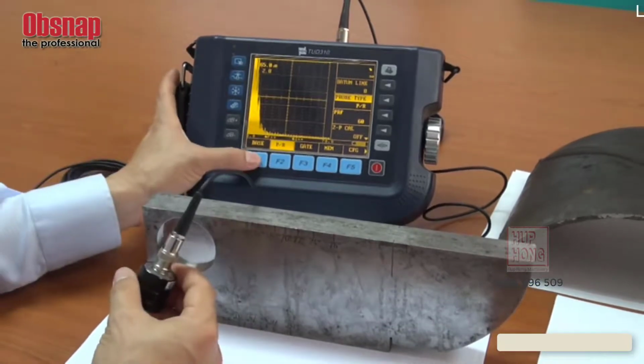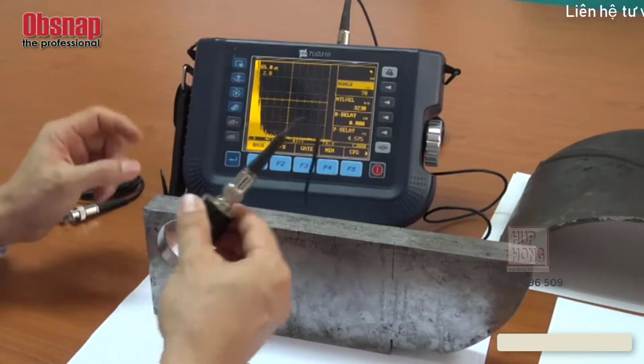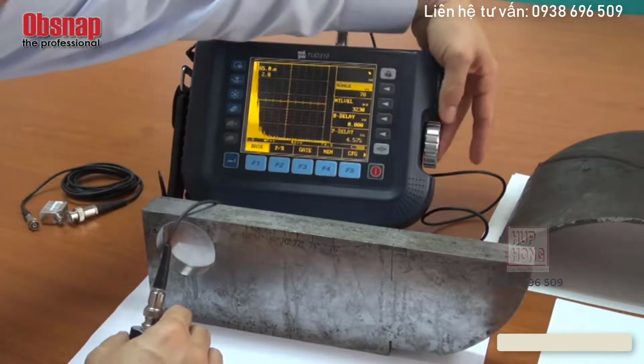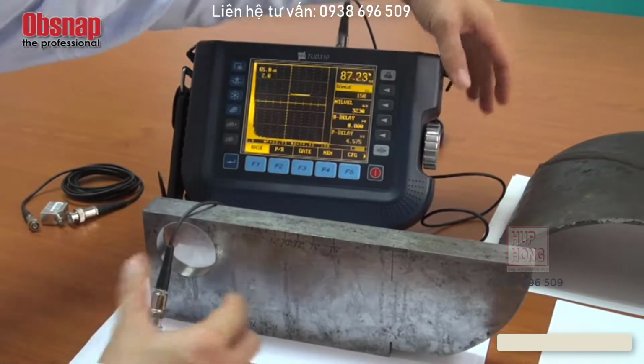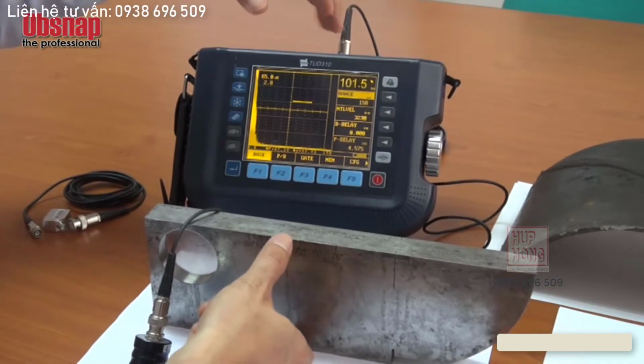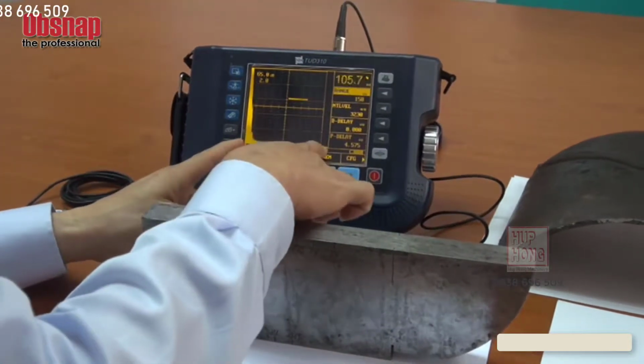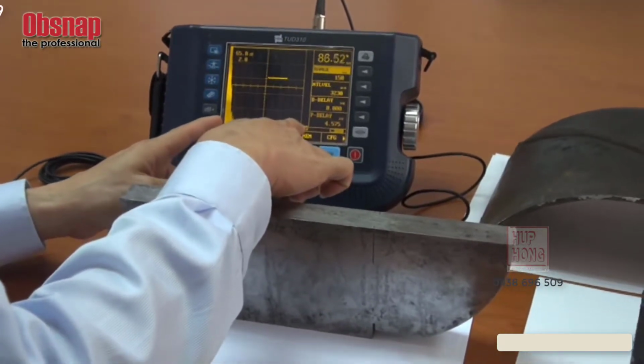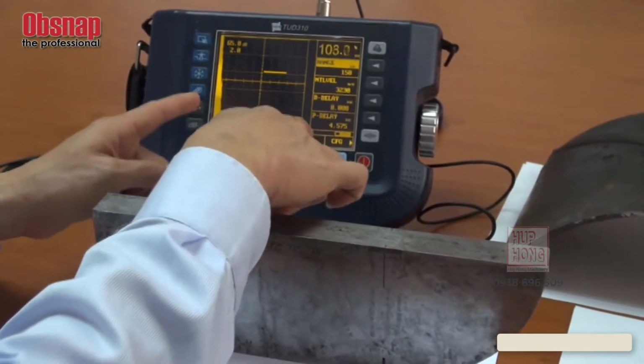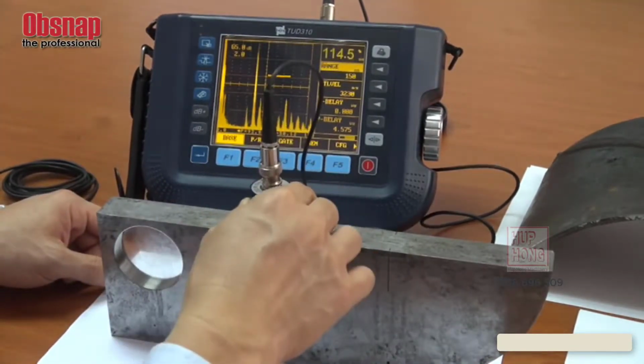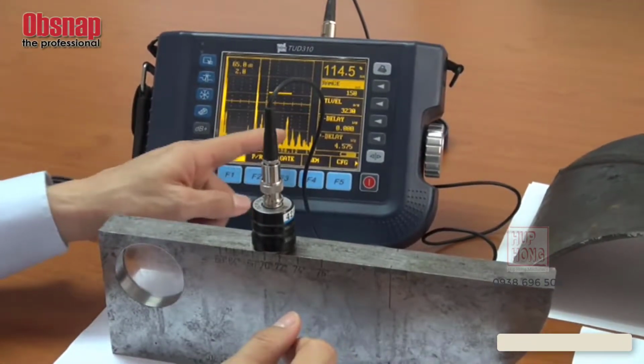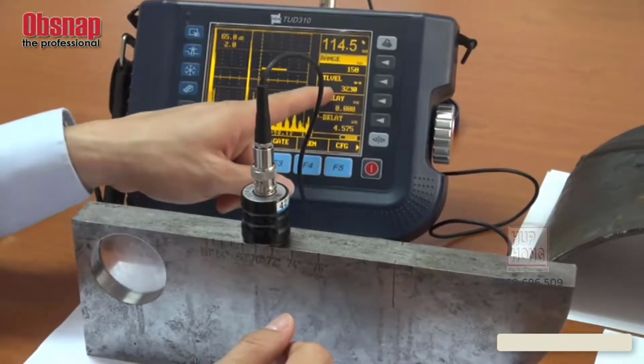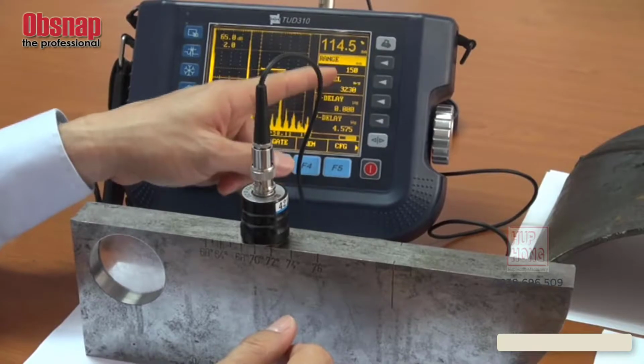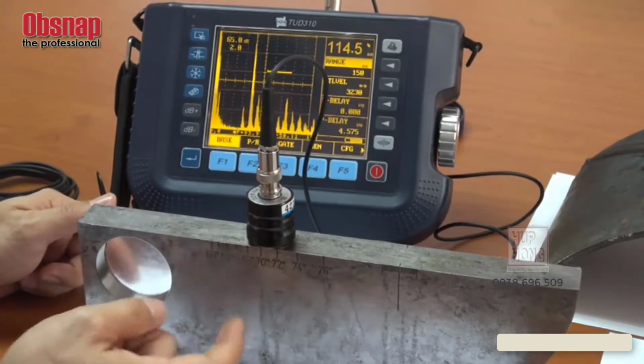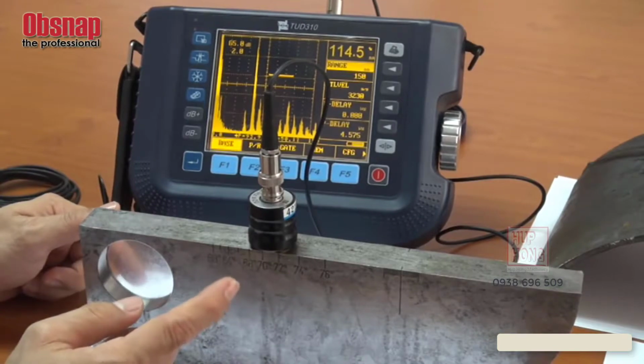Once we have selected, it is time for us to go for calibration. We must set the range that we want to measure, 100 mm. The range that we set is here. This is the x-axis range, so of course it could be at least 100 mm or more. So we put it on top. Well, we are getting so many pulses. What does it mean? Number one, we must check what the velocity is. The velocity for this straight probe, when we are using a straight probe on this material, steel, is actually 5,900. So we must set the correct setting.